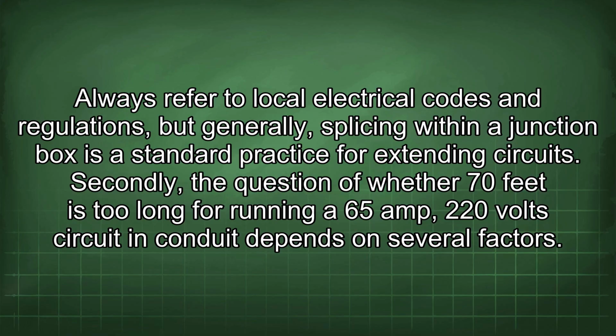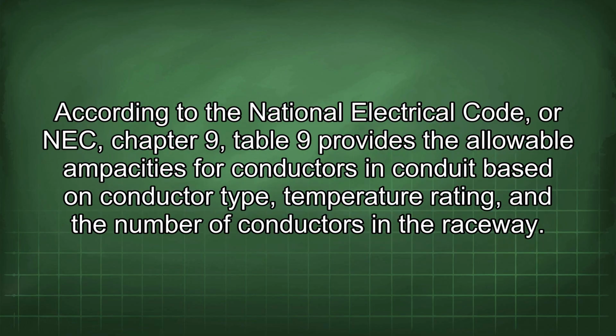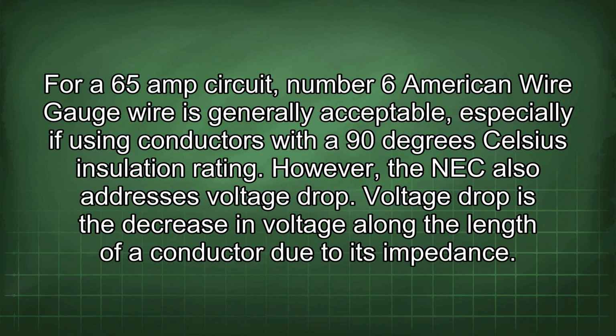Secondly, the question of whether 70 feet is too long for running a 65 amp 220 volts circuit in conduit depends on several factors. According to the National Electrical Code, or NEC, Chapter 9, Table 9 provides the allowable ampacities for conductors in conduit based on conductor type, temperature rating, and the number of conductors in the raceway. For a 65 amp circuit, number 6 American wire gauge wire is generally acceptable, especially if using conductors with a 90 degrees Celsius insulation rating.